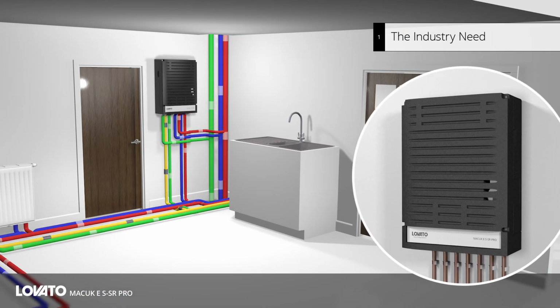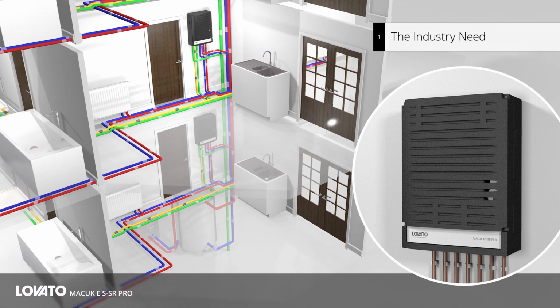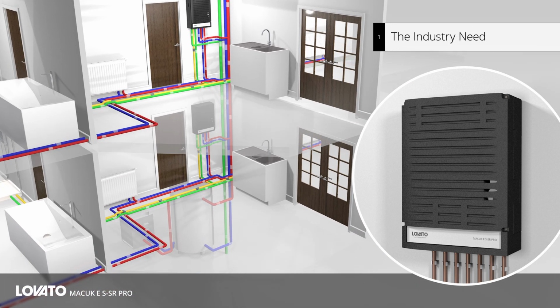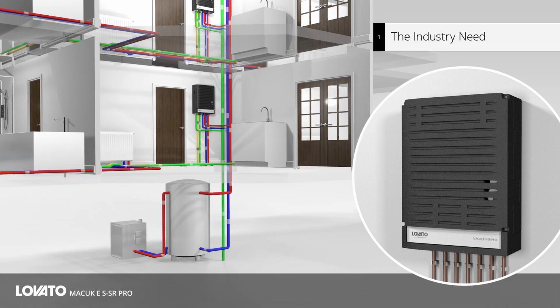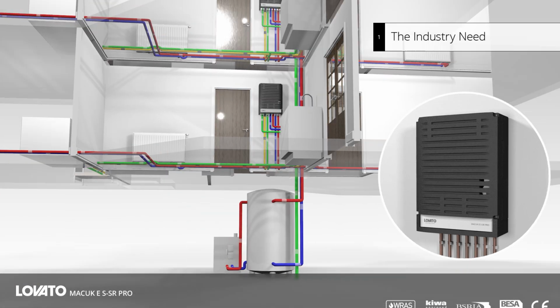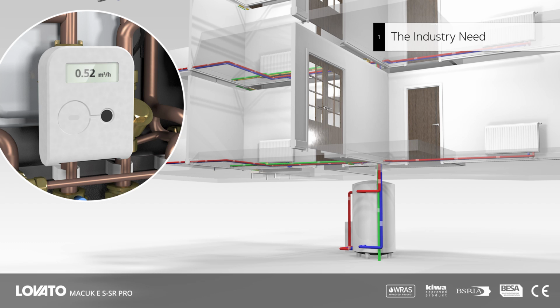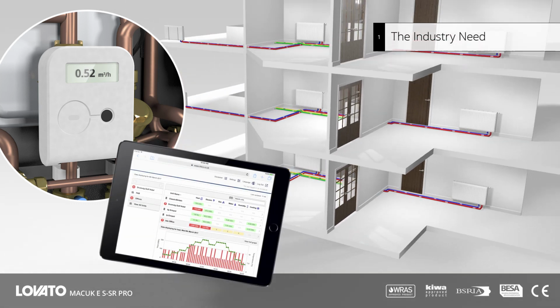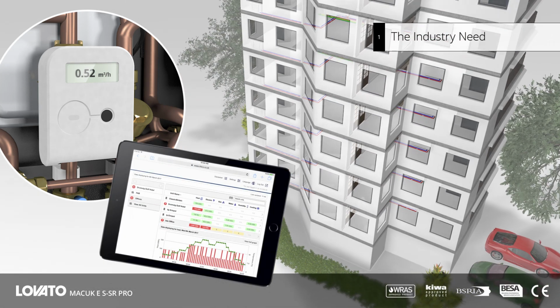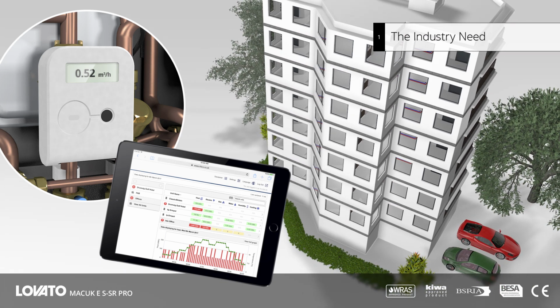Heat interface units act as a bridge between the central plant primary circuit and each apartment, and via built-in heat exchangers provide instantaneous heating and hot water. By introducing an inline heat meter into the design, energy consumption for each dwelling can be accurately measured, reported and charged accordingly.